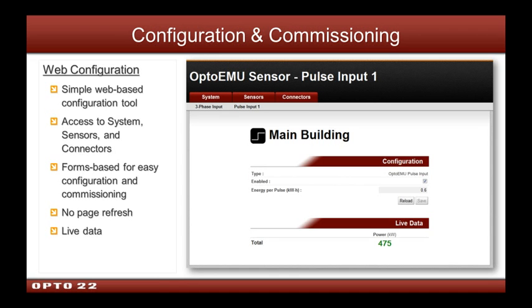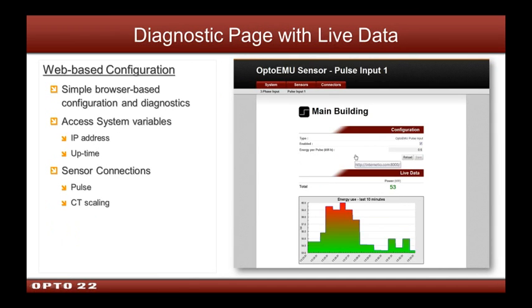The way that the device is configured is through web-based configuration tools. So you put an IP address in it with a little utility that we have, you hit that IP address, and then similar to how you would configure, let's say, a router in your home, there's basically web screens to help you scale your pulses, scale your CT inputs, etc. So, for example, here this shows we're doing a pulse input, and here at Opto 22 we contacted our utility and they told us that one pulse represents 0.6 kilowatt hours, so we scaled it there. So again, we've tried to make it so it has more of a broad appeal to people not familiar with control systems.